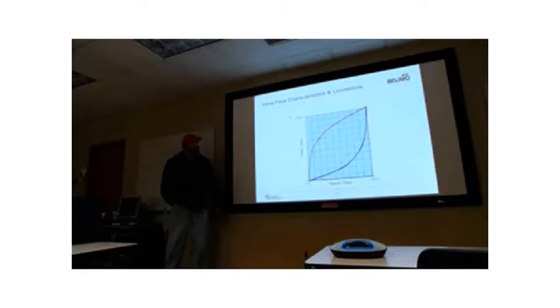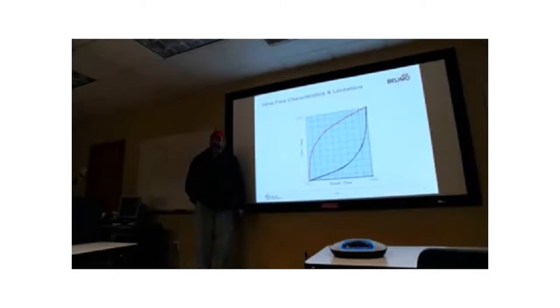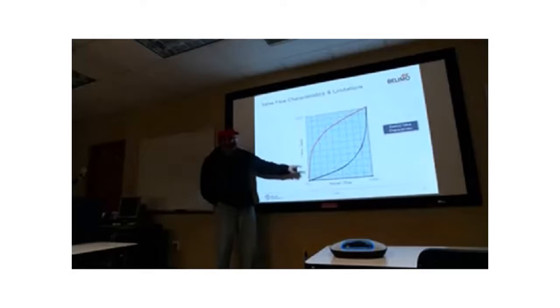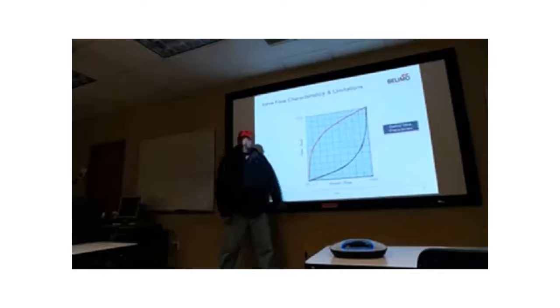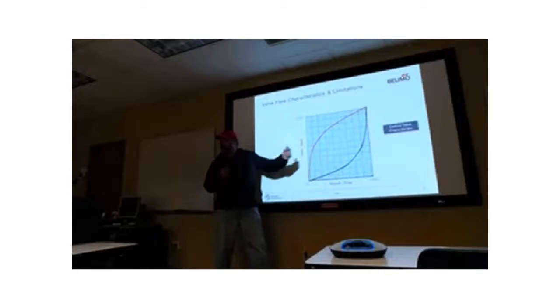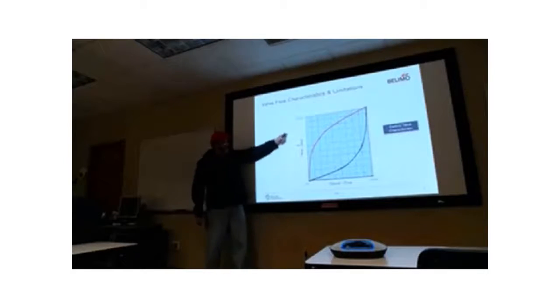How does that work, right? What's going on? Well, here's what's going on. There's another thing to consider here, okay? So we start out and say, okay, there's the control valve characteristic, right? And when you're looking, these are actually two plots slammed onto the same graph. So the blue line is the signal to the valve, or the opening of the valve, right? 0 to 100%. And then on this axis is going to be the flow of water through the valve, right? And that's that one there.